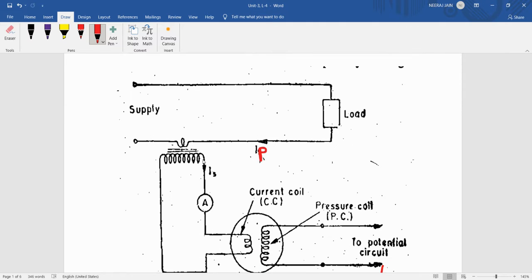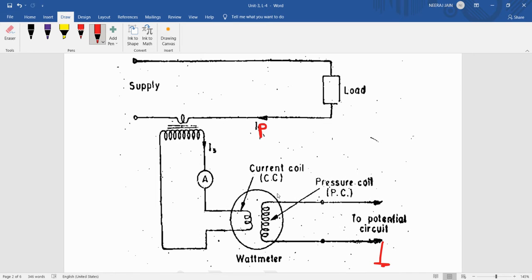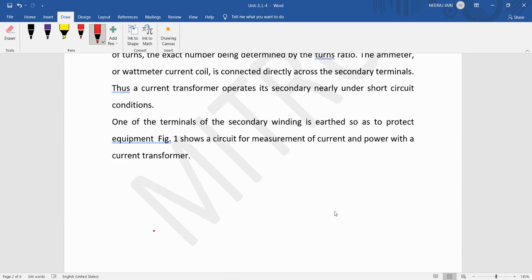So we can see the current transformer is like this. It contains the line voltage and line current connected with the primary winding. This is the secondary winding, and that is the current coil and pressure coil of the wattmeter, connected to the potential circuit.